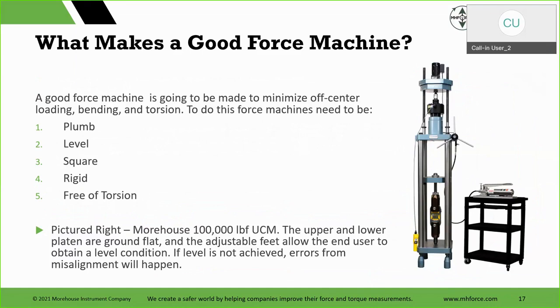Oh, this will work. But they end up introducing all this additional error and they don't do the ILC or the proficiency test to know that they actually have the error. So that's a lot of hidden error. We've done all the tests in the cal machines. So we know that our errors are really, really low when it comes to comparing 2 standards calibrated in deadweight against each other. So pictured right, here's a 100K UCM, upper and lower platen are ground flat.